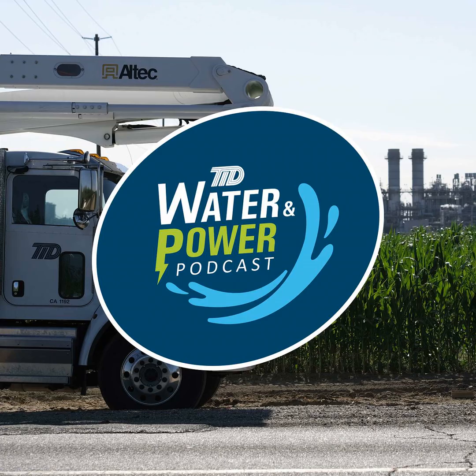So that's kind of the projects there for substations. And then we also have our distribution and transmission upgrades. There's some issues to where you have certain contingencies that happen. For example, if one transmission line, or we call it all elements in service, I'll go back, where every transmission line is in service. And let's just say you have one contingency happen, a line trips based on a fault or a certain issue on that line, and the breaker opens up, and now that line is open and de-energized. Well, how does the system now move those electrons for power flow?